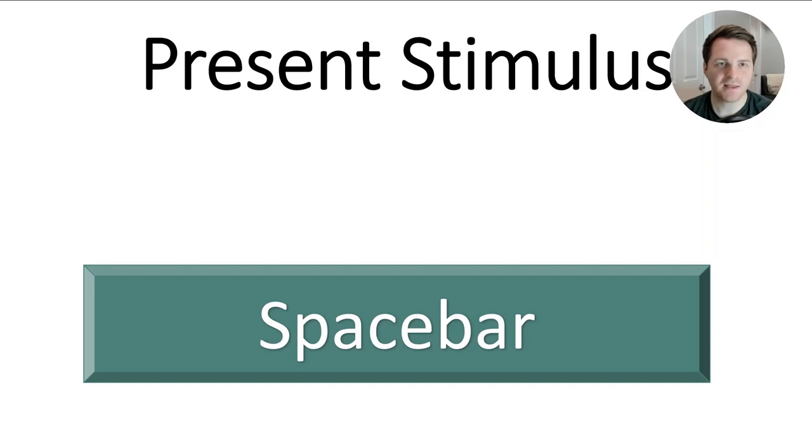The first shortcut is to present the stimulus. In the audiometer, you can hold down the spacebar to present the stimulus. Be sure to keep it held down for at least three beeps or you'll get a flag.